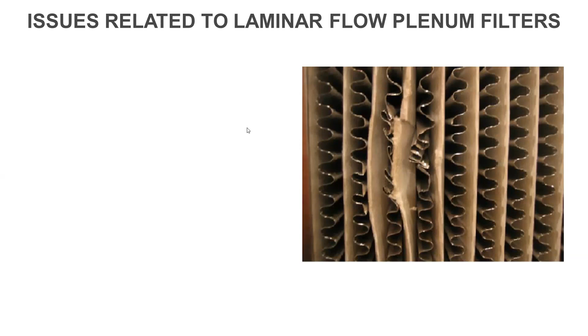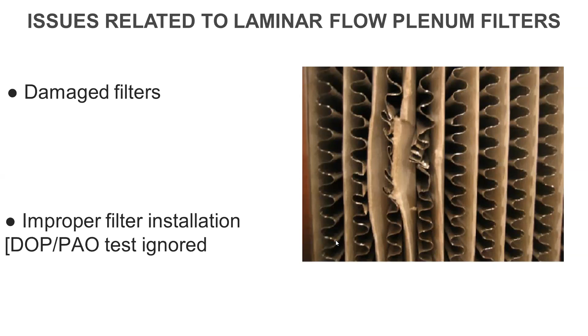It really acts like, the simile that I've got is an AK-47. So what happens is all the pathogens come out of that hole, like shot after shot. Especially as you've got a laminar flow, the flow is straight. So if by mischance you've got a surgical site which is just below, then these pathogens will actually be shot into that particular zone. And the chance of surgical site infection is that much more. So it is not just about the pinhole, even the installation all around, you have to ensure that laminar flow is intact, and it has to be tested from time to time visually, and also with the DOP and PAO test, that is called. So these are the issues.